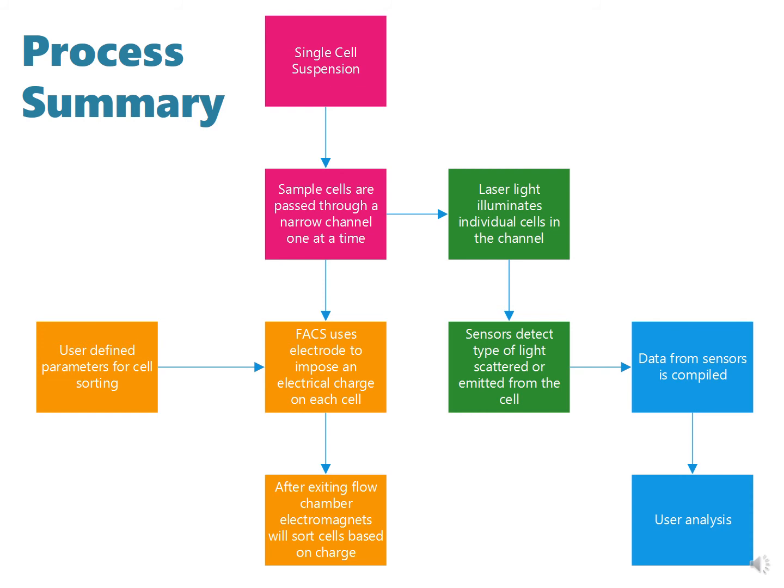In summary, the process starts with a single cell suspension that is passed through a narrow channel one at a time. Laser light illuminates individual cells in the channel and scattered light as well as fluorescent emission is picked up by the detectors. These detectors, in turn, convert this information to a digital signal. The signal can then be analyzed by the user.